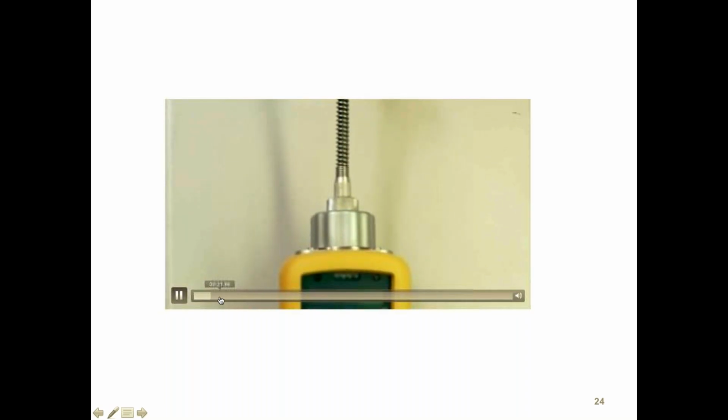The UV lamp ionizes volatile organic compounds. The ionized gas then passes over a sensor which detects the charge and then converts that signal into a current. The current is then amplified and displayed on the unit as a reading in parts per million. The MiniRAE 2000 detects VOCs at a range of 0 to 10,000 parts per million. It features real-time readings and data logging capability.